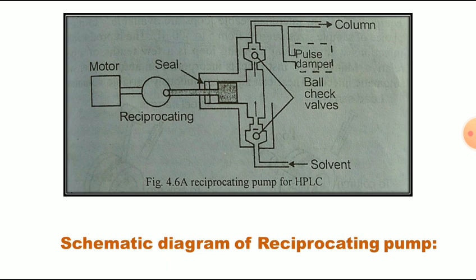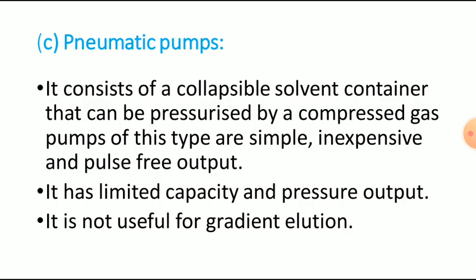Now we will see the third pump, that is pneumatic pumps. Okay, pneumatic type of pumps. It consists of a collapsible solvent container that can be pressurized by a compressed gas. Pumps of this type are simple, inexpensive and have pulse-free output. It has limited capacity and pressure output.